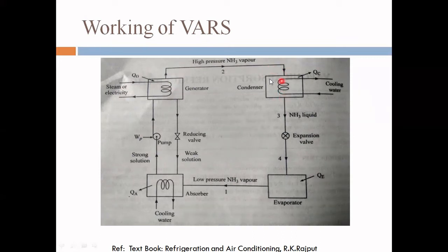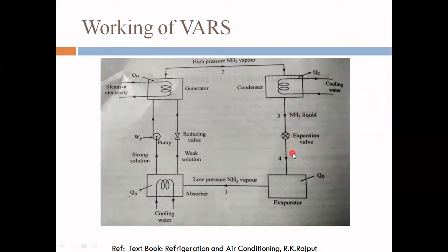The high-pressure NH3 vapor goes to the condenser, where cooling water is used to convert it into liquid NH3. Condensation takes place here. After the condenser, the high-pressure NH3 liquid passes through the expansion valve, which converts it into low-pressure, low-temperature NH3 liquid.